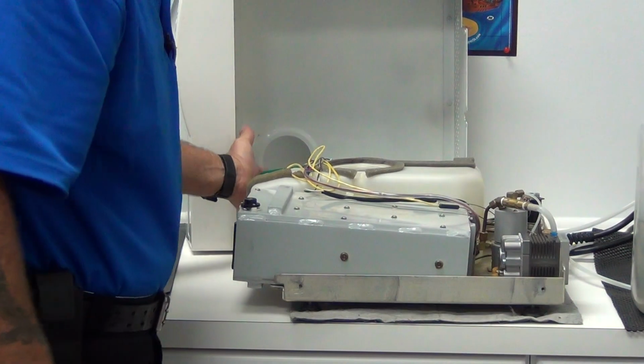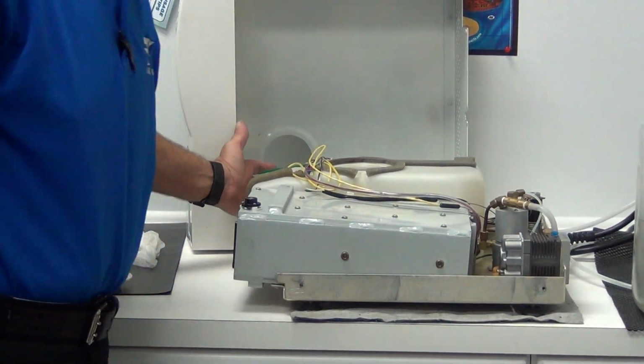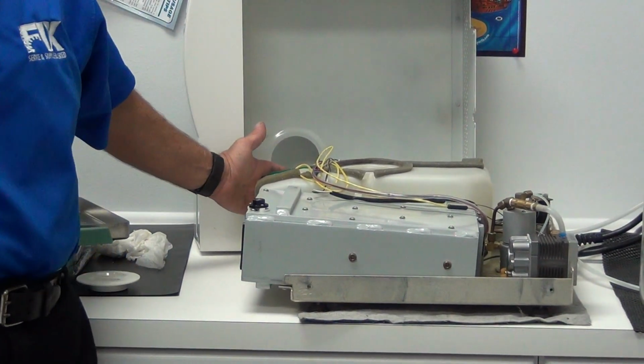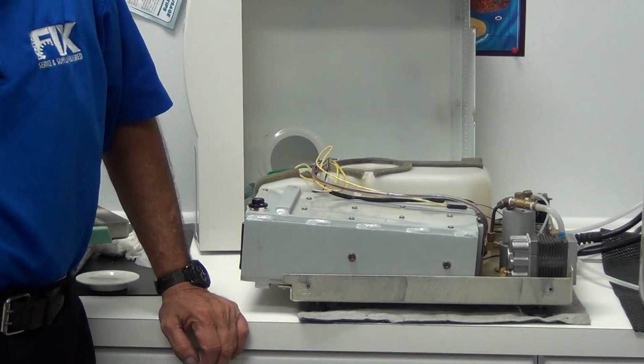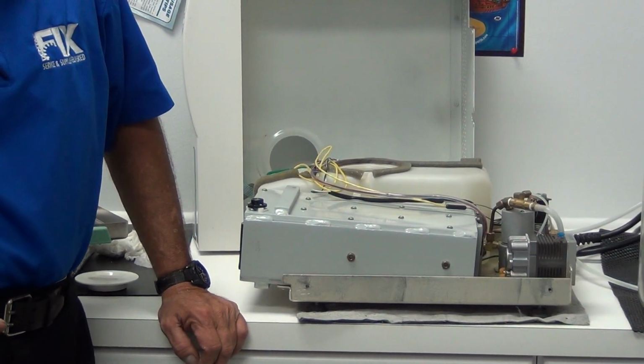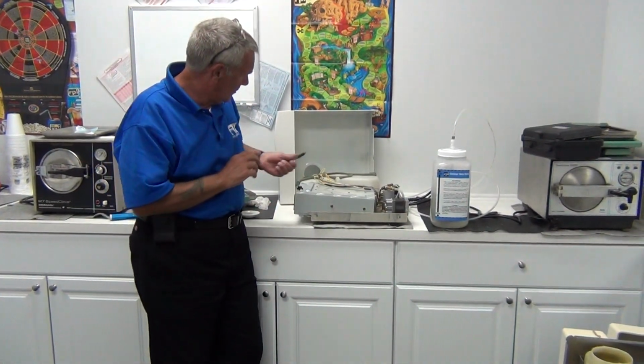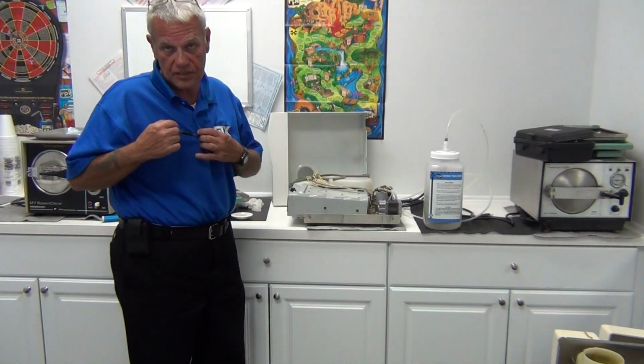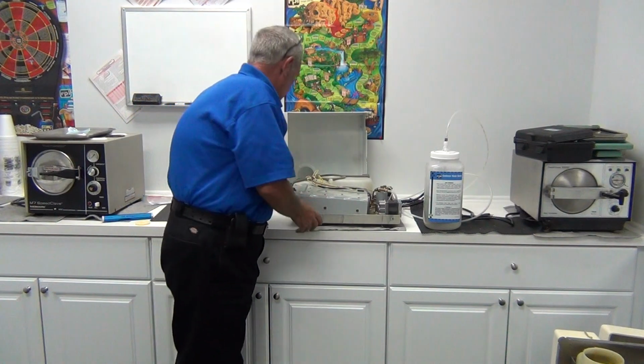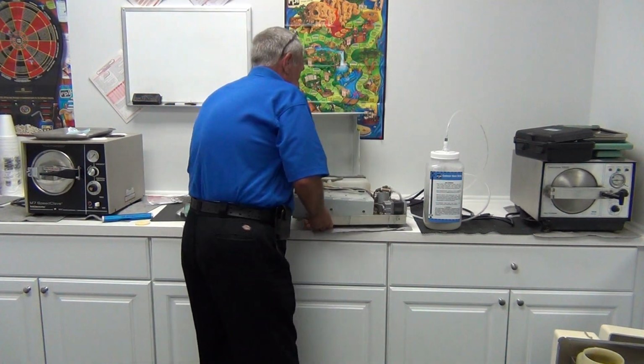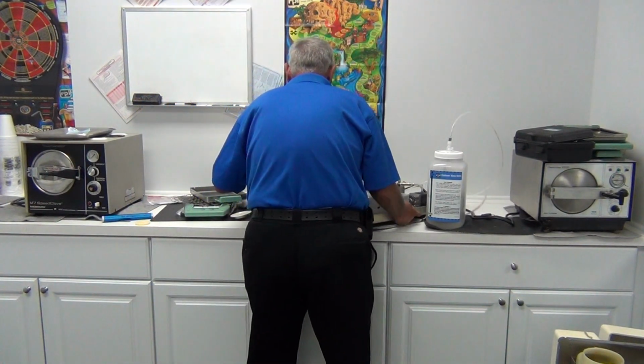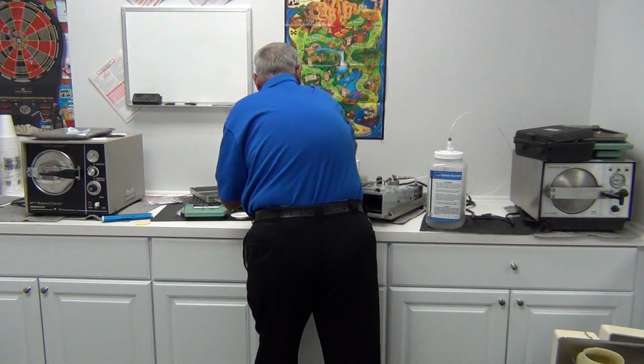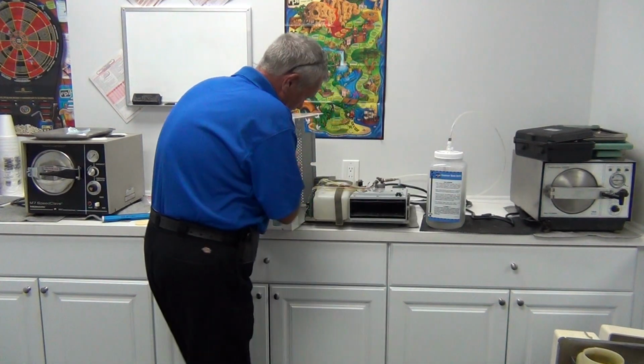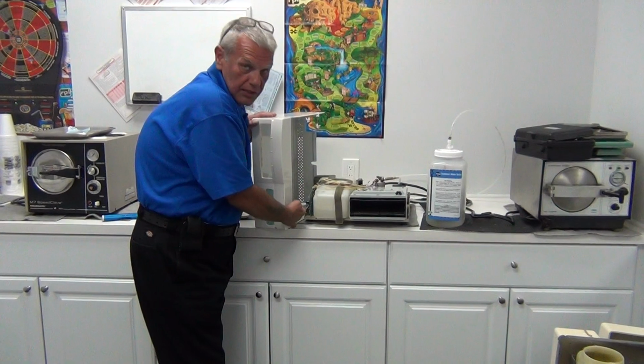This cover has ribbon cables that attach it to the circuit board. If these ribbon cables are broken or not oriented correctly or polarized correctly when they're plugged back in, the machine will do all kind of craziness. It will look like it's reading out its script in a foreign language. I'm going to turn the machine, excuse my behind here, so we can all see the ribbon cables.